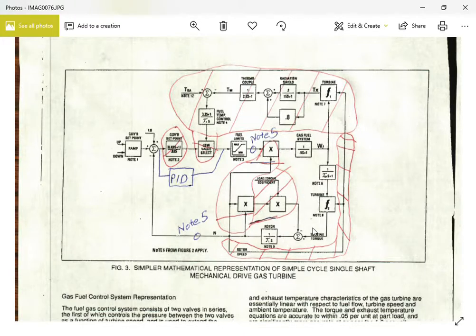I also took it out here, rotor speed, on the turbine speed calculation, because if I multiply by 1 here and divide by 1 here, I haven't actually done anything. So this simulator only works around full speed. But in fact, speed control is only used near full speed. So we don't have to multiply and divide by 1 at various places, unless I really want to use this for part speed or to see how I would deviate down to 90% or something. So anyway, that's why I took those out.